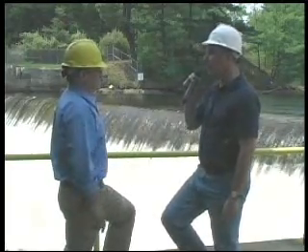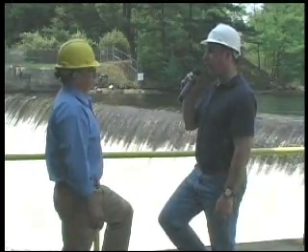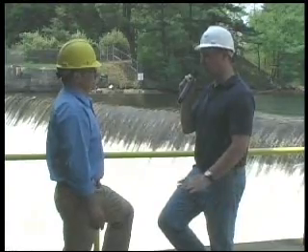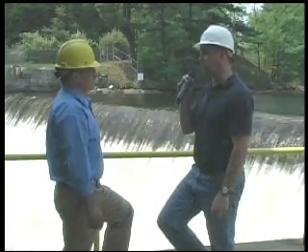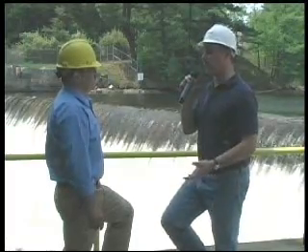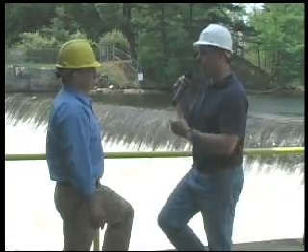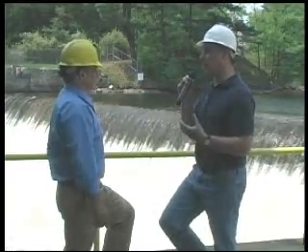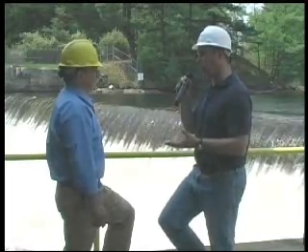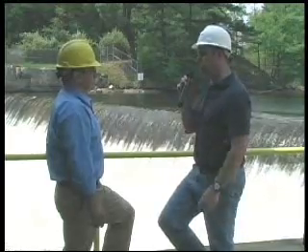That's a good question. During the drought conditions, which is a typical summer, where there is less flow that comes down the river than we can generate, we shut the unit down and do not generate. We do not produce any electricity. And we're a run-of-river facility. In other words, whatever water appears into our impoundment, that's what's got to pass. So if there's only, for example, 5 CFS that comes down the river, essentially that 5 CFS is distributed across the top of the flashboards.